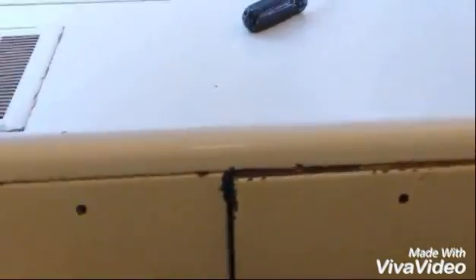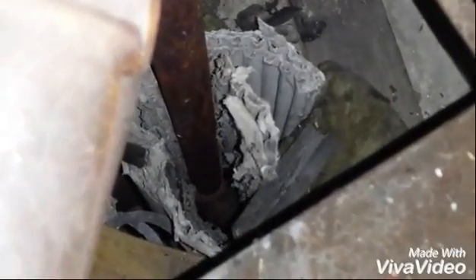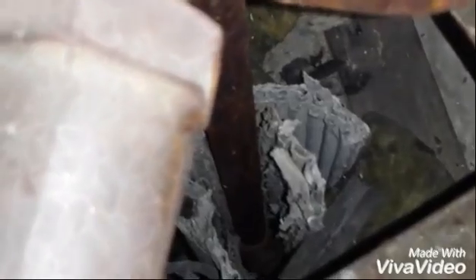I've worked on these, and in almost every one — in every room — you're going to find this inside the cabinet. You see that insulation that's open-ended, that looks like the end of cardboard? That is asbestos air cell insulation, and it's just in terrible shape in these cabinets. Any time there were asbestos elbows on these pipes in the cabinets, they just knocked the crap off, and it's all down in there — those chunks there.